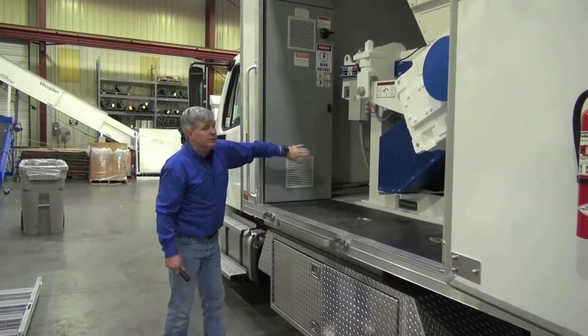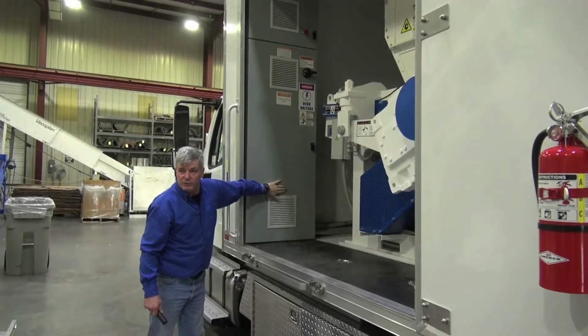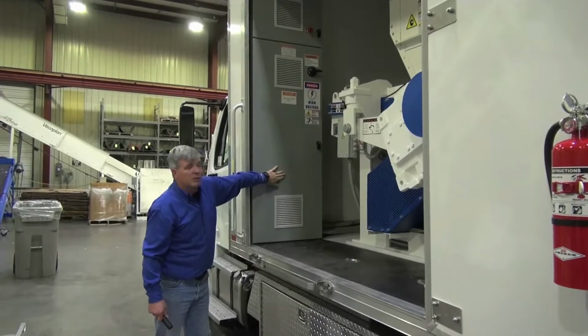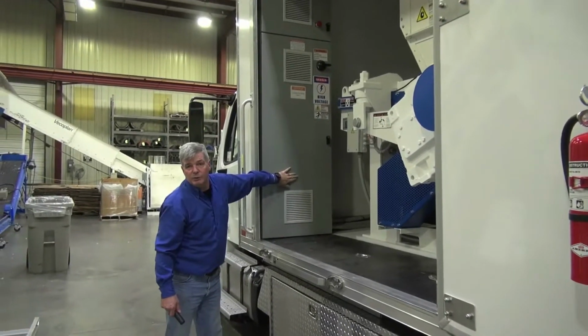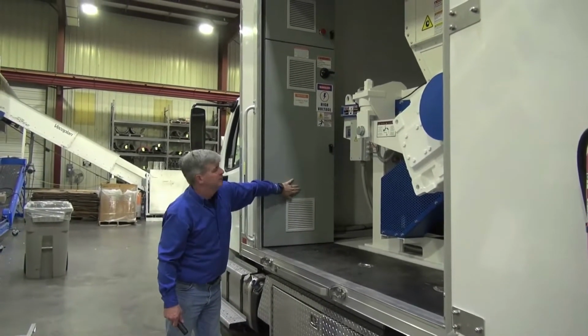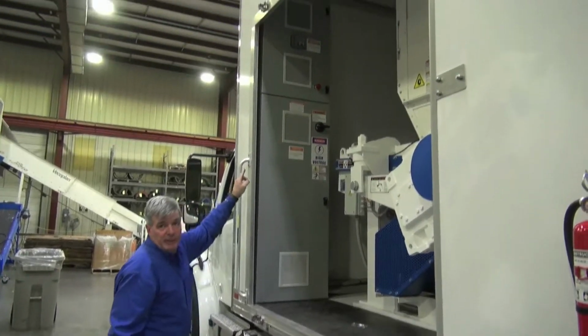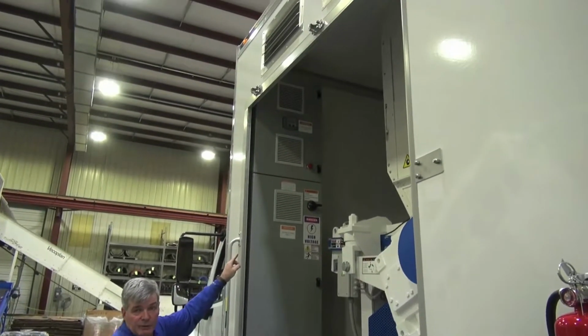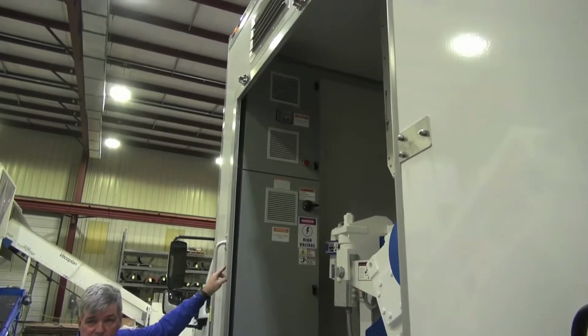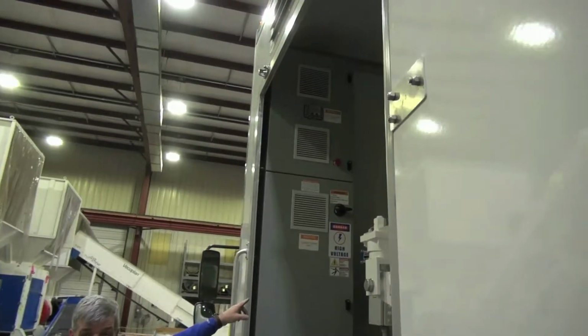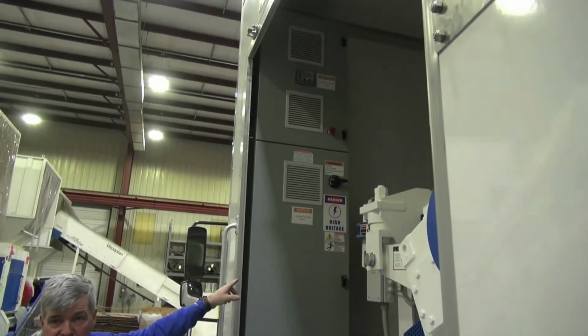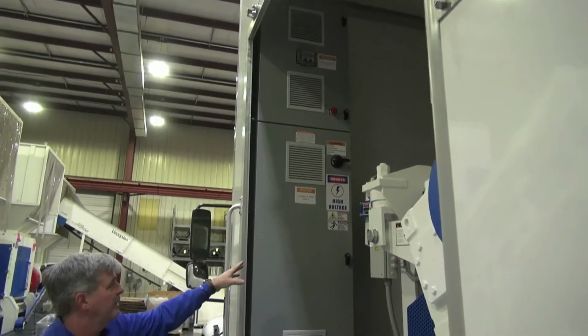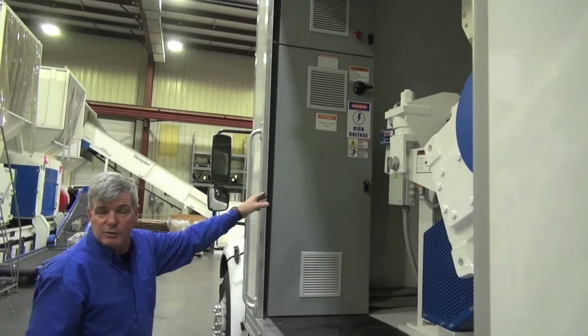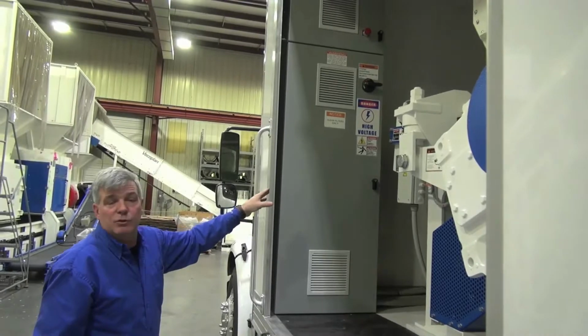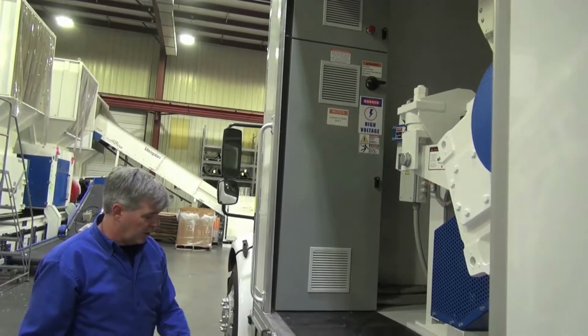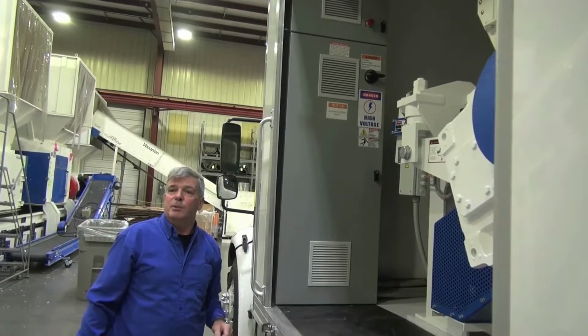The 460 volts are fed into the bottom end of this control panel. The bottom of the control panel houses all the high voltage components. The top of the control panel houses all of the low voltage components. These are placarded high voltage, and it is only recommended that qualified electrical knowledgeable people go into this control panel while the generator is running or the plant power is plugged in.